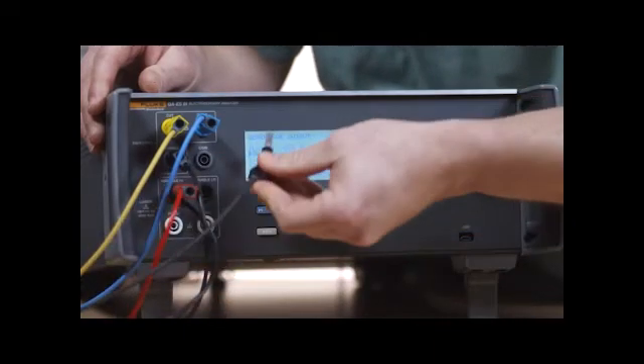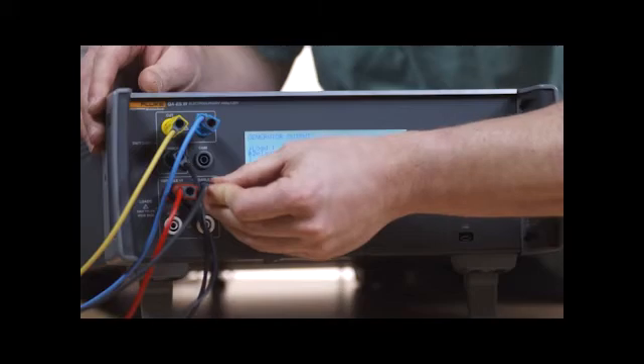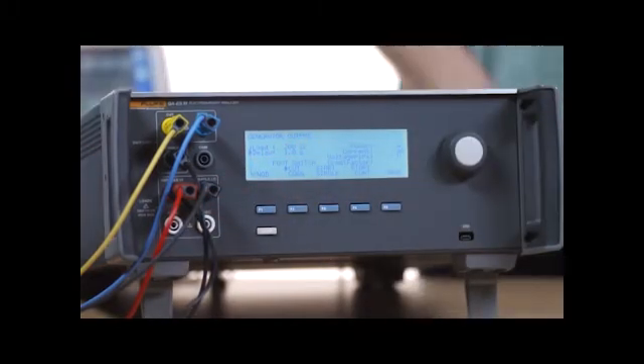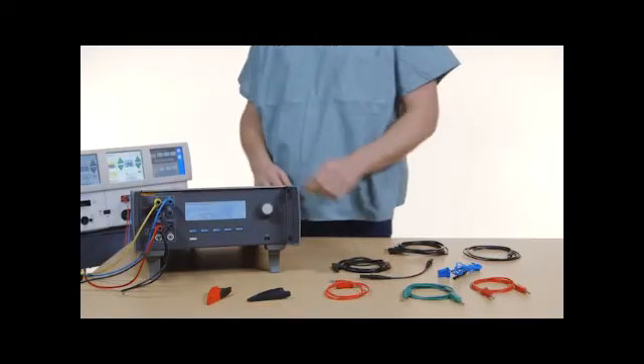Use a stackable connector to connect one of the ESU neutral electrodes to the variable load jack. Connect the shorting leads between the neutral connections on the ESU.